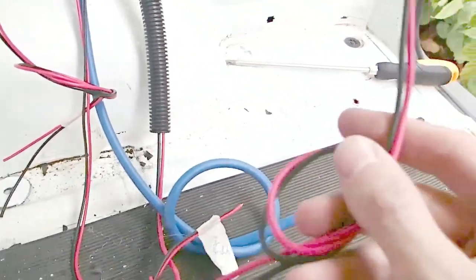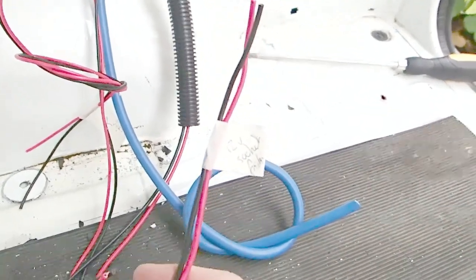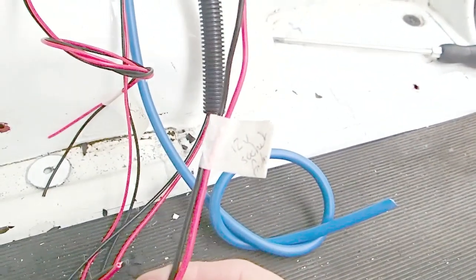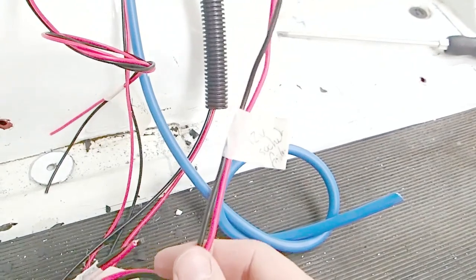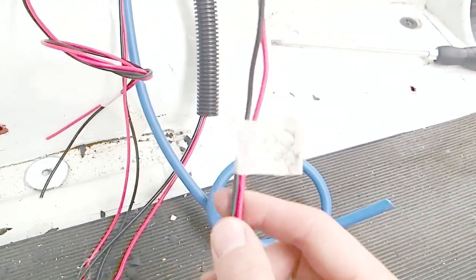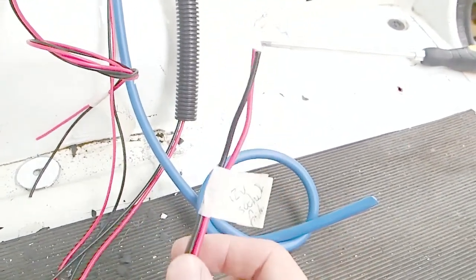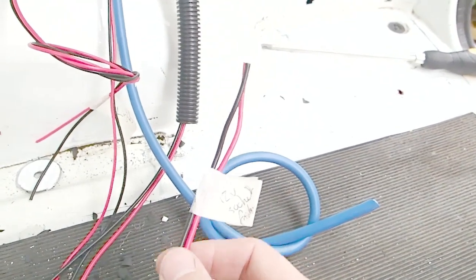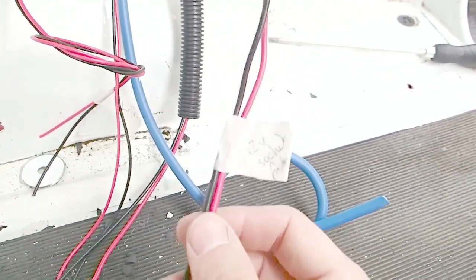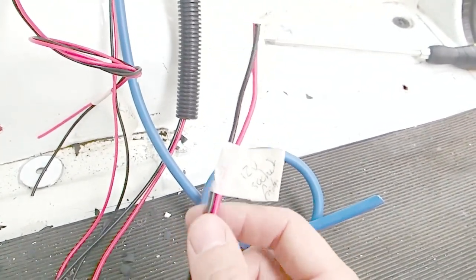For example, my 12 volt socket is a good example. The maximum it will draw is 5 amps, so I wouldn't want a 5 amp cable for it because I need to add that additional 25%, which would be 1.25, so I need something that's at least 6.25 amps.